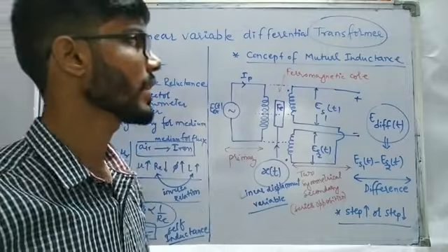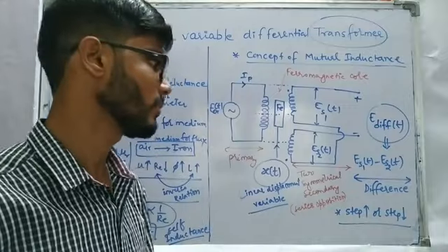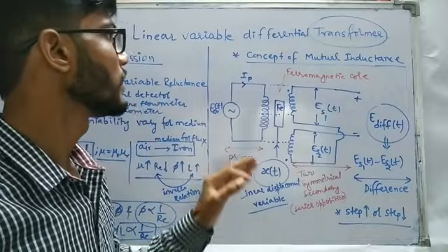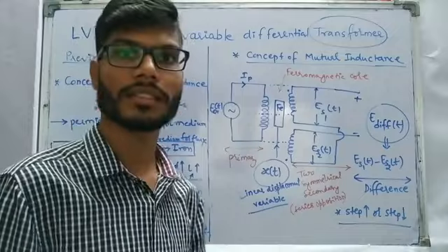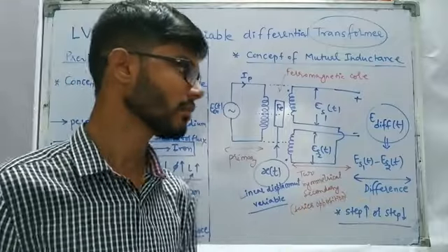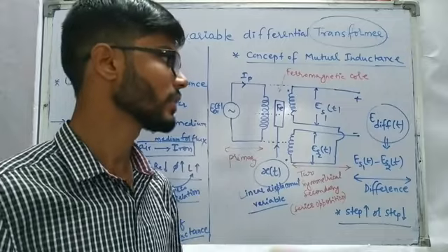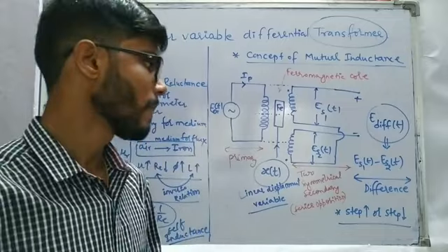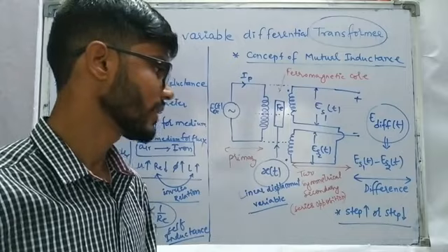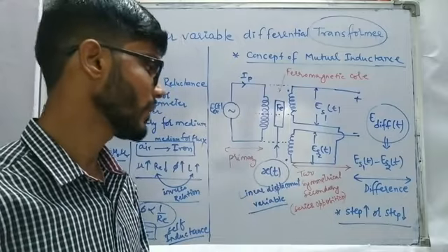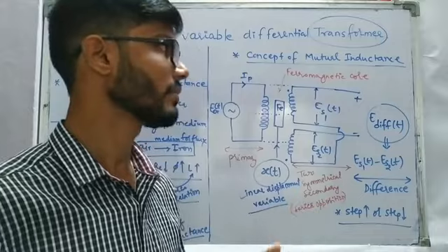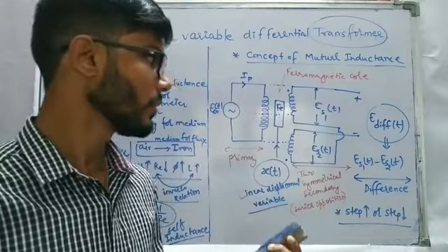Let's look at why we call it a Linear Variable Differential Transformer. 'Linear' because the displacement provided to the system is a linear input. 'Differential' comes because of the series opposition of the secondary windings. And 'transformer' because it can step up or step down voltage based on the primary and secondary number of windings. LVDT has one primary winding, two symmetrical secondary windings in series opposition, and one ferromagnetic core.